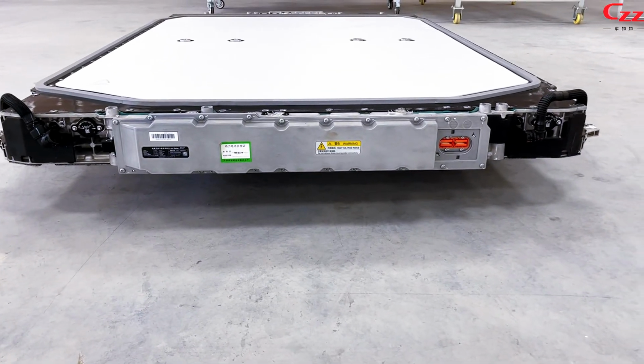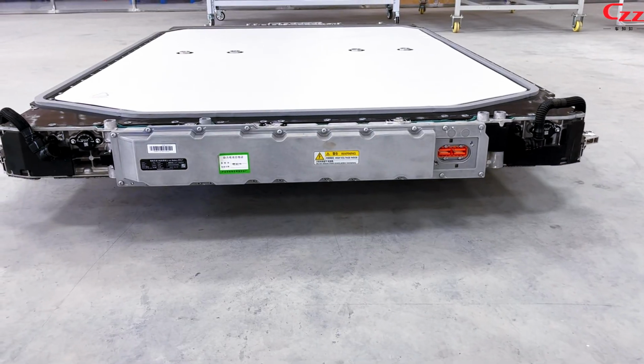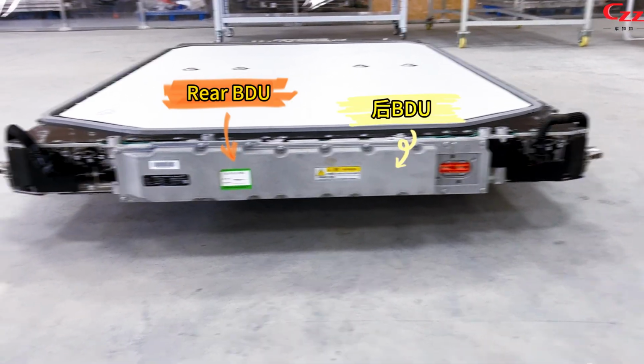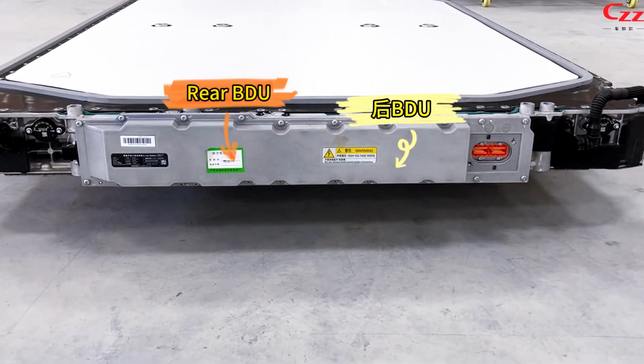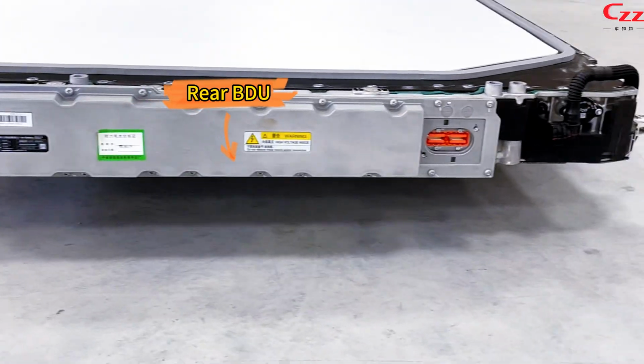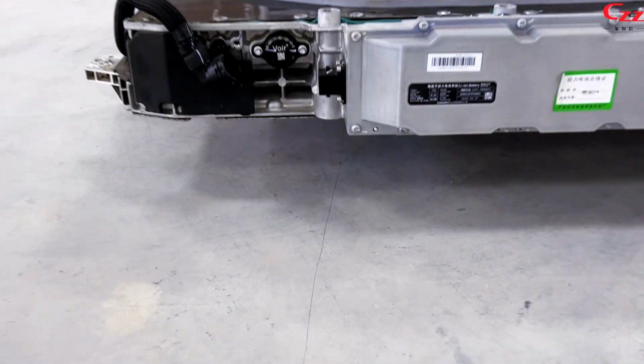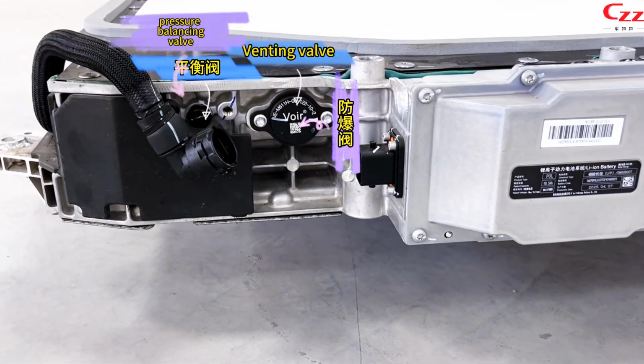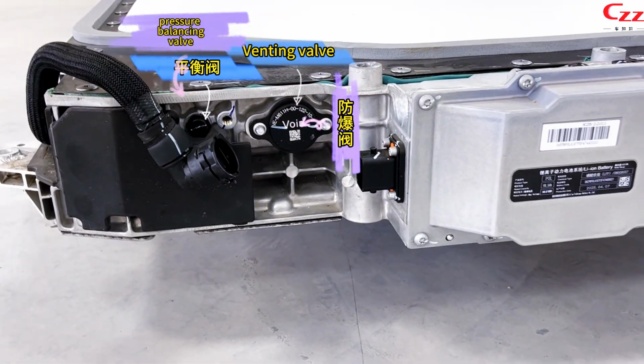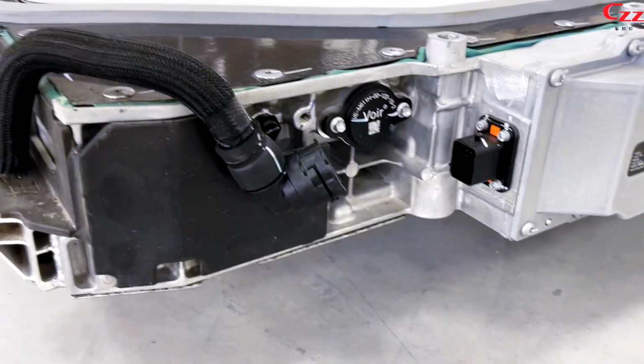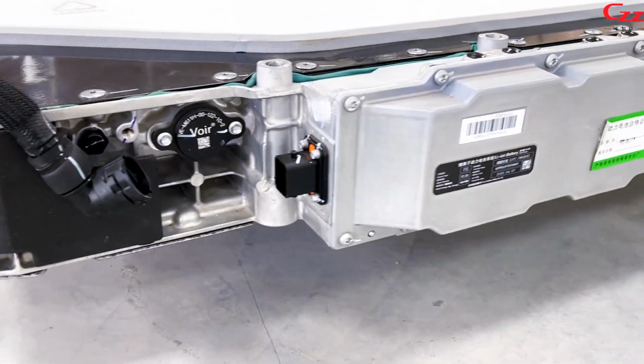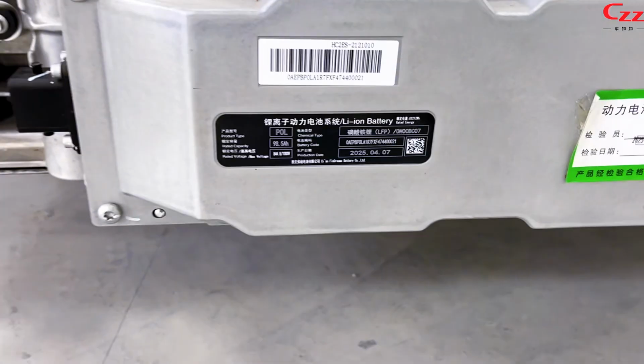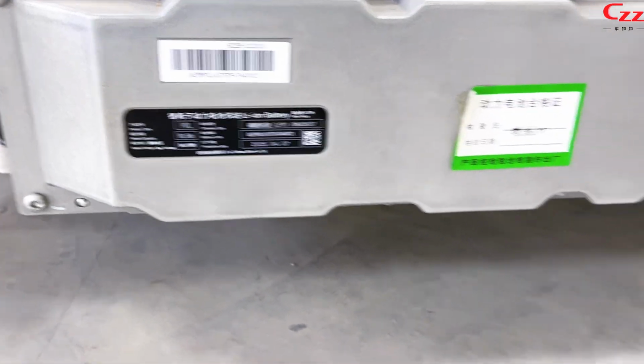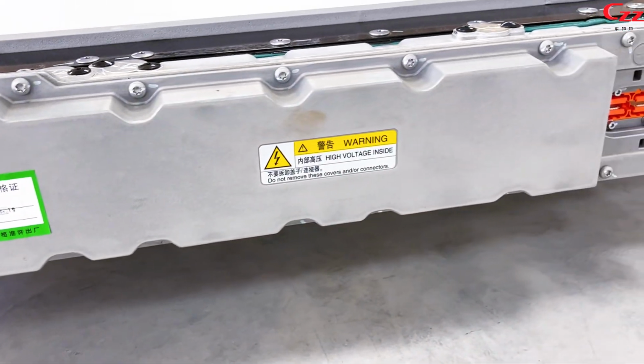Now we see the rear end of the battery pack. There is a larger BDU, the battery disconnect unit, located in the middle. At the left side, there are the venting valve and the pressure balancing valve. From the nameplate, we know the rated capacity and rated voltage, which gives the rated energy at about 83.2 kilowatt hours.